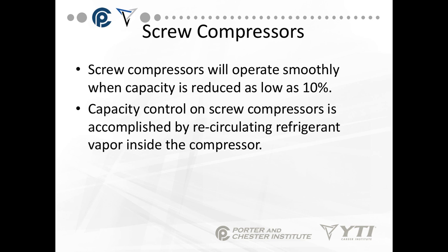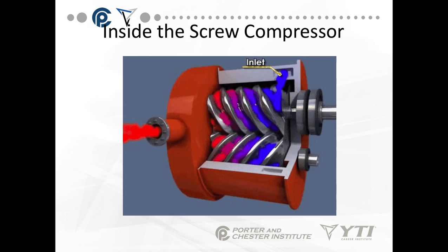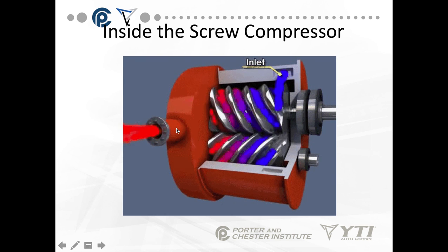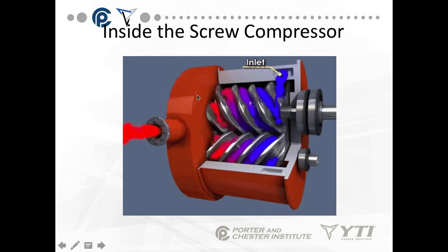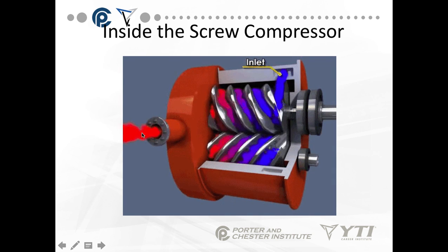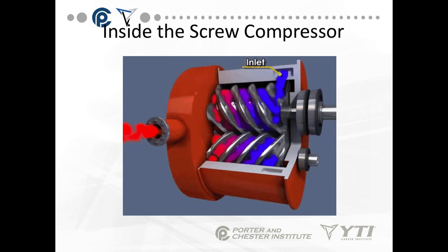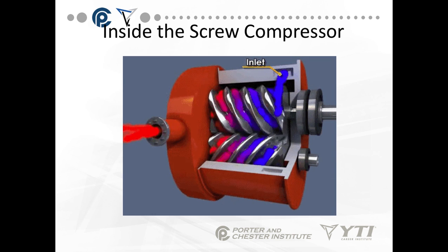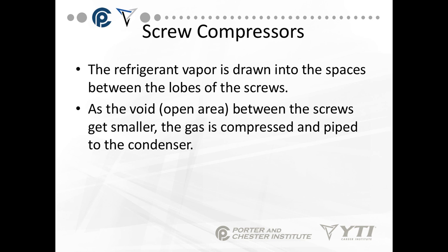Screw compressors operate smoothly even when capacity is reduced as low as 10%. I can reduce the flow of refrigerant or reduce the speed of the compressor and lower capacity to about 10%, ramping up and down depending on demand. Capacity control on screw compressors is accomplished by recirculating refrigerant vapor inside the compressor — taking some discharge vapor and allowing it to come back into the inlet. More recently, we can also control capacity with variable-speed motors. The refrigerant vapor is drawn into the spaces between the lobes of the screw; as the void gets smaller, the gas is compressed and piped to the condenser.